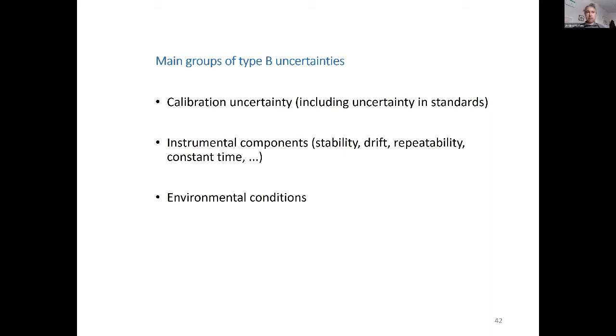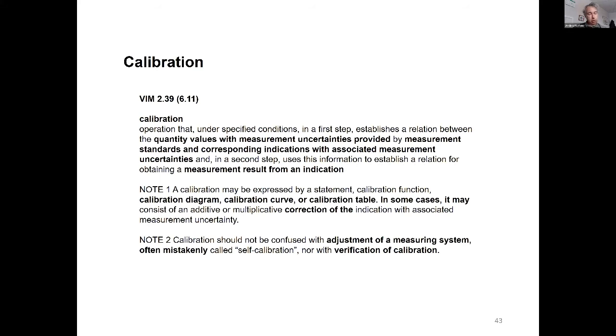The calibration, it is given by the guys who calibrate your instrument. The instrumental components, you need to know them. Stability, the drift, how well you use it in field. There is something that comes from the manufacturer, but something that you may want to evaluate, and something, for example, that comes from intercomparison of instruments, which you know, well, I don't know exactly how it works, but I have an idea. An intercomparison was done, and this is the result, the mean value of this. And from the environmental conditions. That's the key point for our talk. The calibration, I don't go again into this, is the operation that allows you to correct for systematic error by comparing your device with respect to a given reference value with the associated uncertainty.